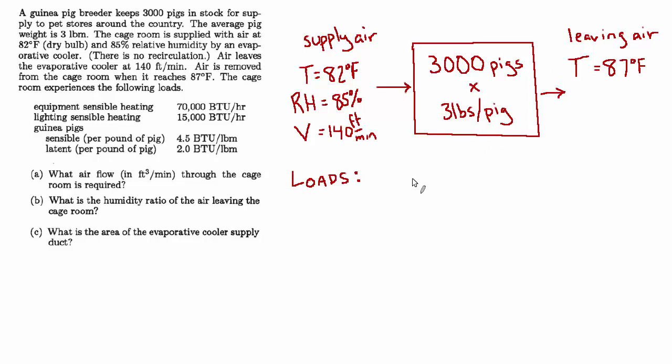I'll break it into two columns, sensible and latent. And I'll just say all the units are BTUs per hour, so we don't have to write the units over and over again. So we have this sensible load from equipment, that's 70,000. And then we have another 15,000 sensible from lighting. And then from the pigs themselves, we have 4.5 BTU per pound, and there's 9,000 pounds of pig, right? 3,000 pigs at 3 pounds per pig. So 9,000 times 4.5 is 40,500 for the sensible component.